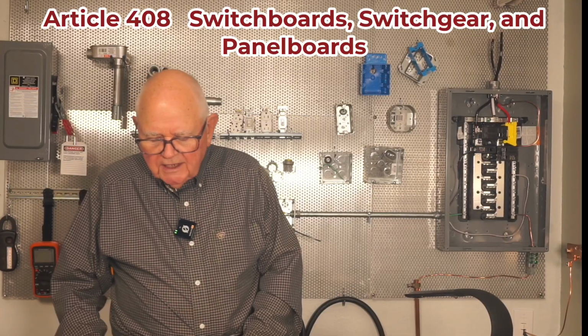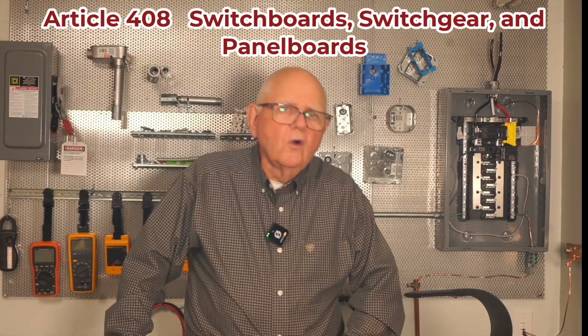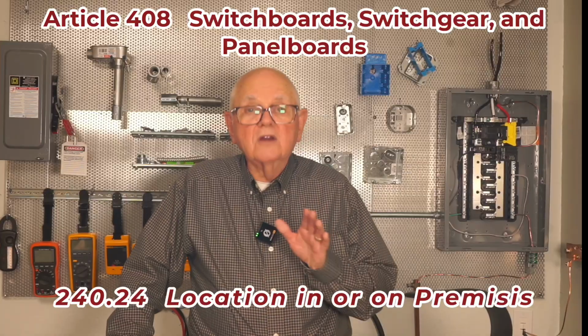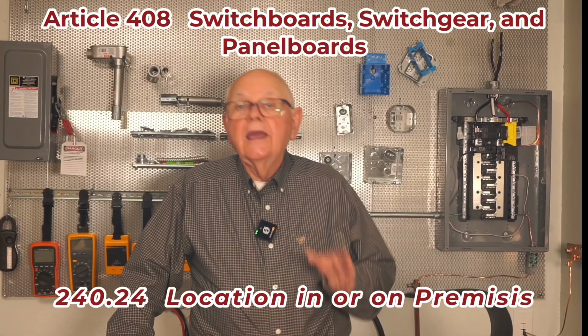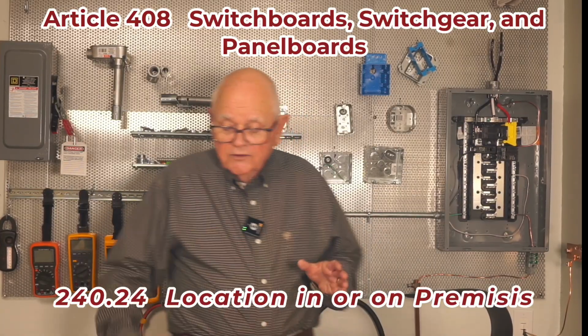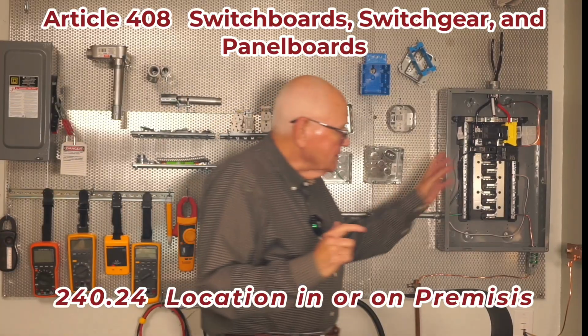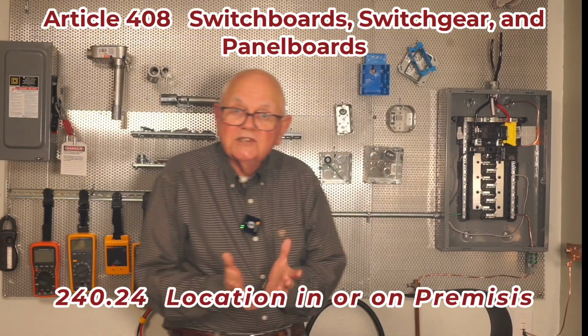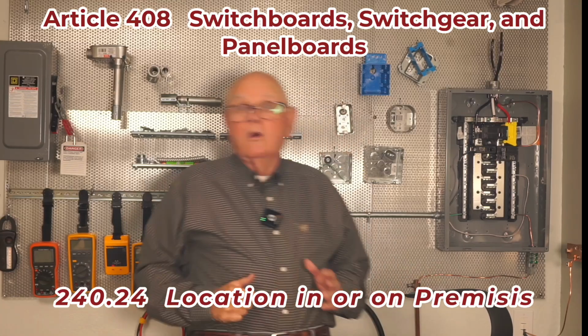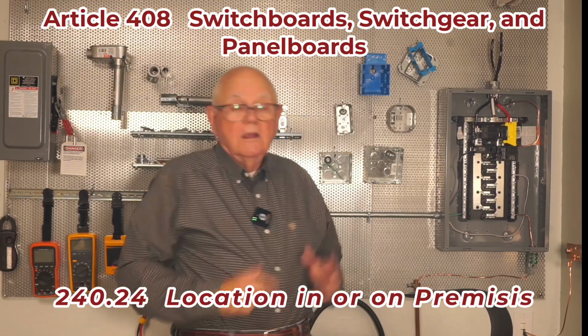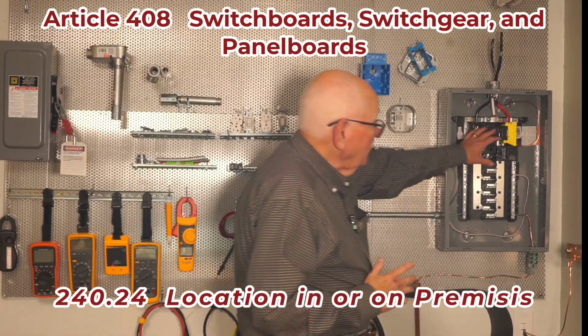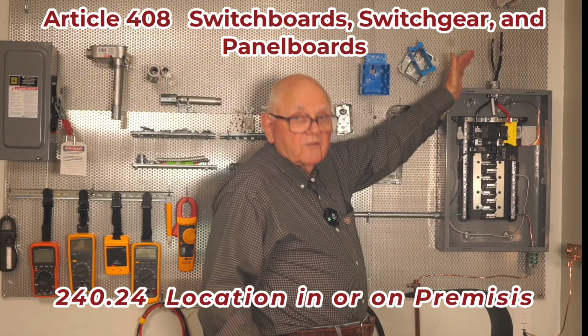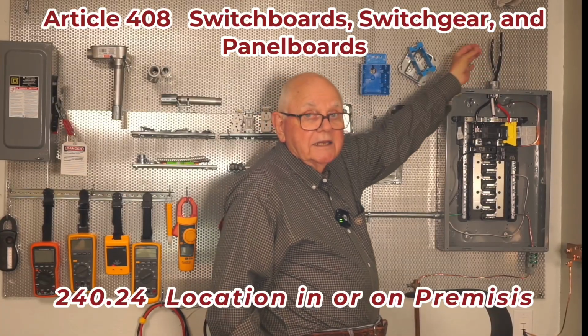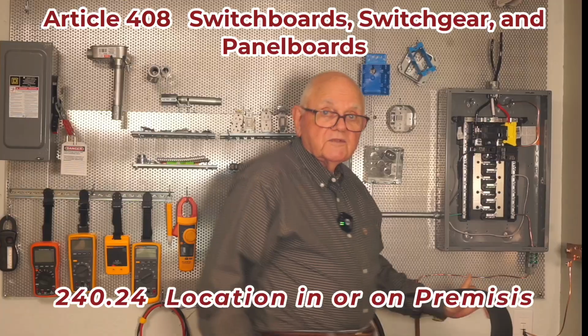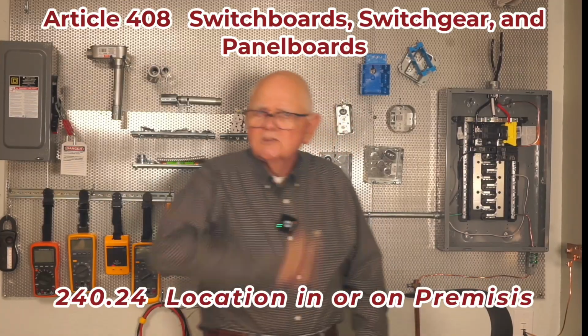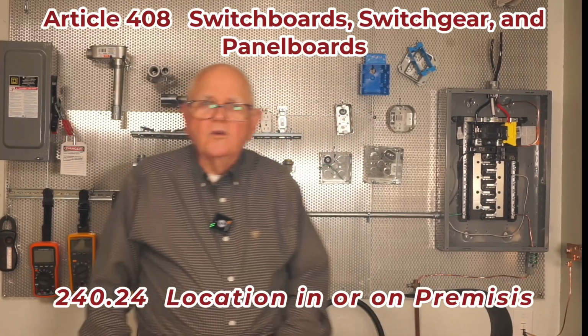And finally, check out 240.24. 240.24, Article 240 on overcurrent protection, talks about how my overcurrent protective devices have to be readily accessible. I have a definition in Article 100 for readily accessible. It also tells me that the center of the grip of the operating handle in the up position can be no more than 6 feet 7 inches from the floor. So check out all your requirements in 240.24.